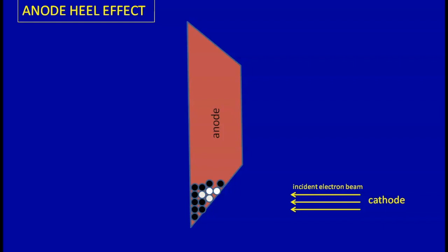This effect stems from the fact that X-ray photons are produced not only at the surface of the anode but also at deeper levels within the substance of the anode. And X-rays are isotropic in nature, that means they are emitted equally in all directions.